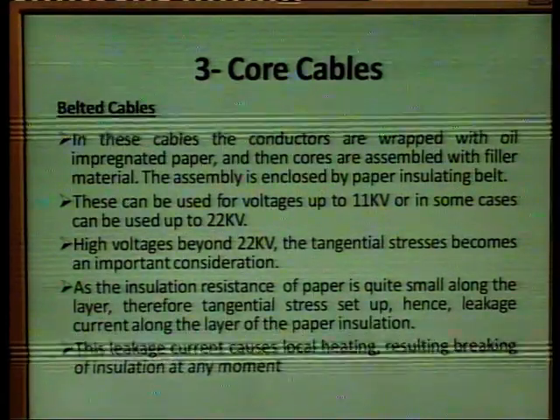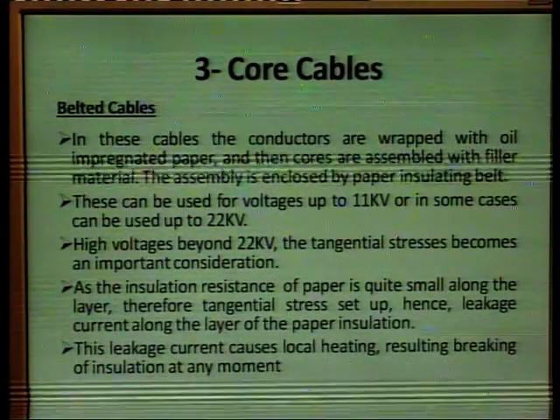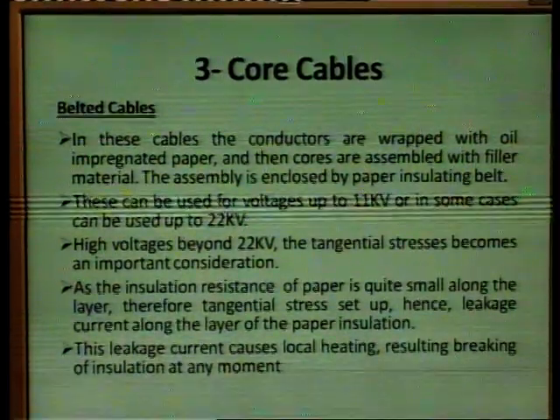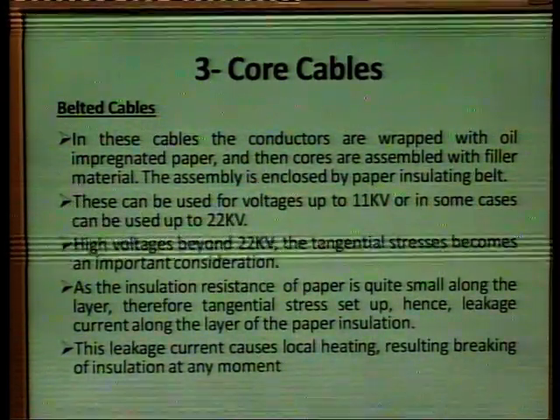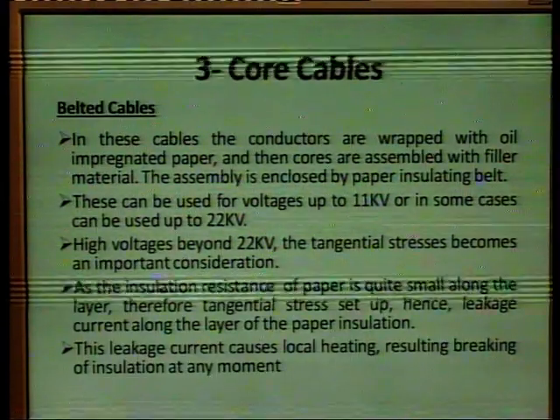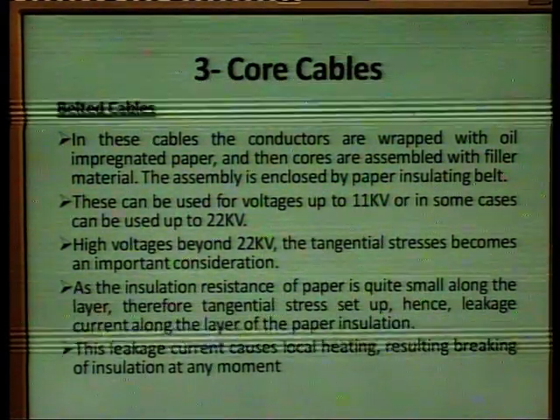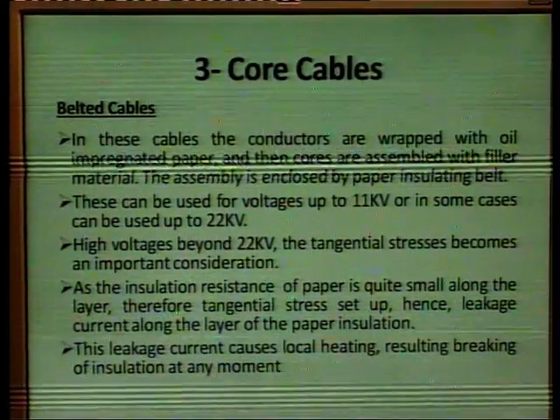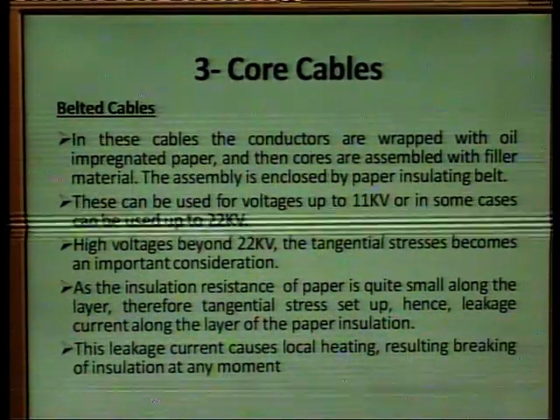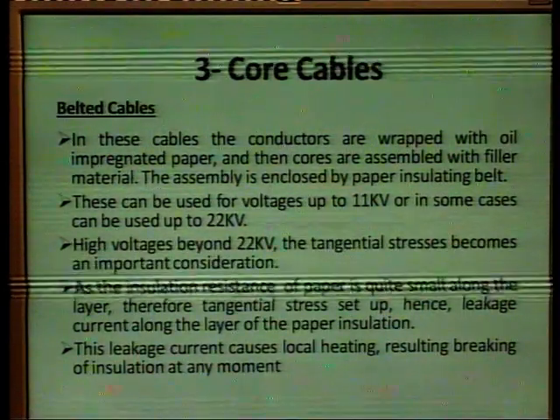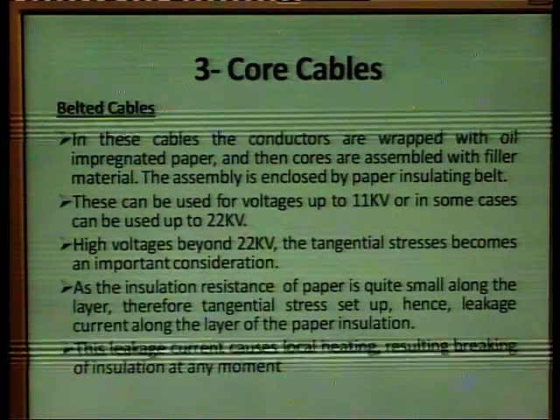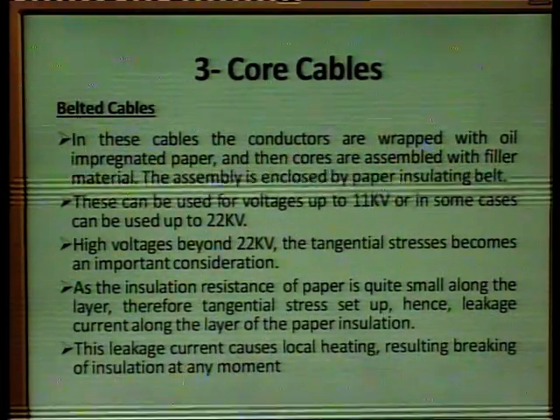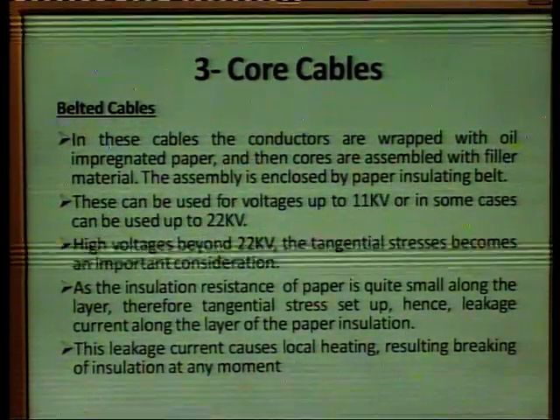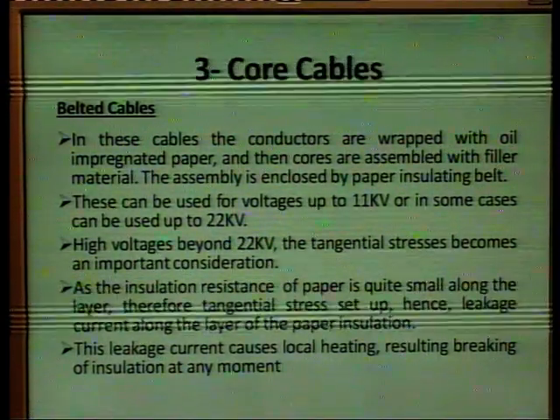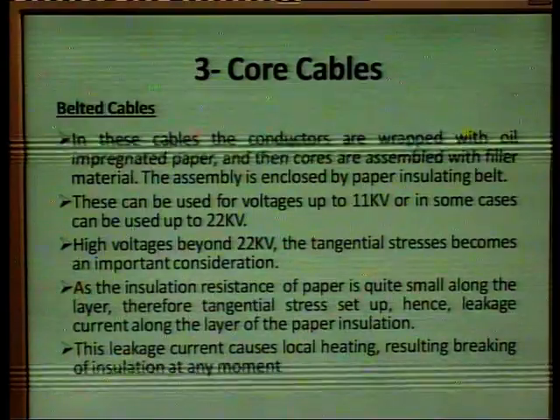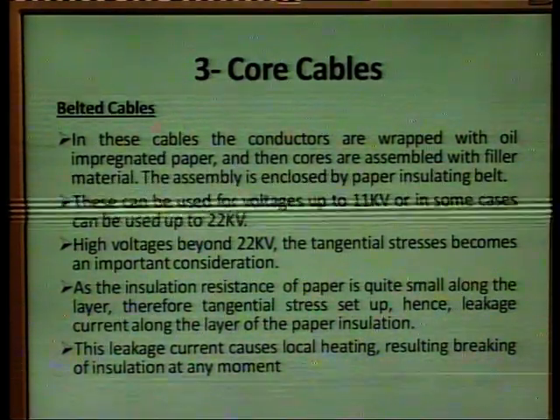So now we have the 3 core cables. First are the belted cables. In these cables, the conductors are wrapped with oil impregnated paper, and then the cores are assembled with filler material, and the assembly is enclosed by a paper insulating belt. These can be used for voltages up to 11 kV, or in some cases up to 22 kV.